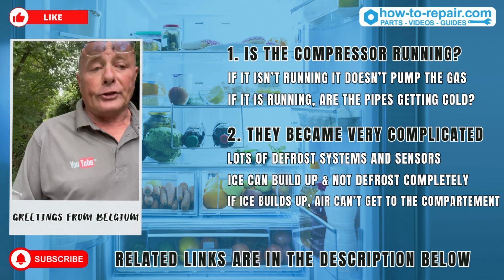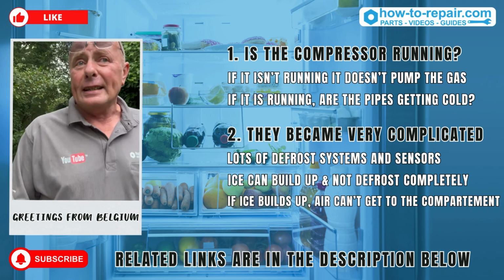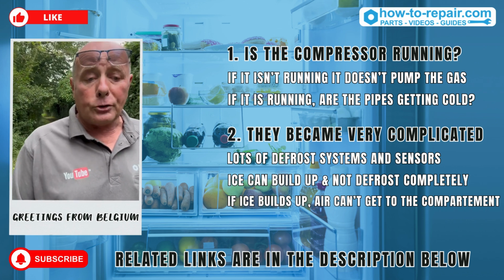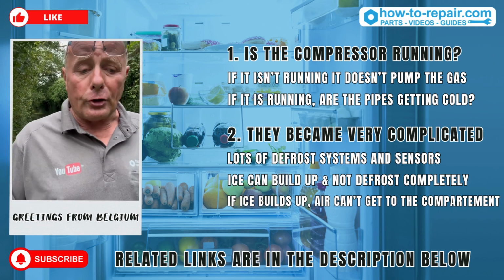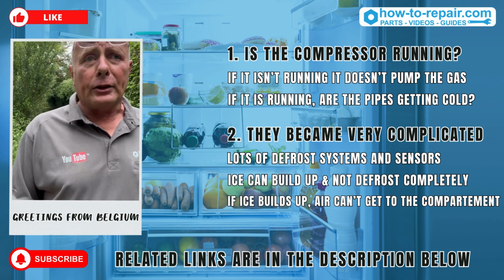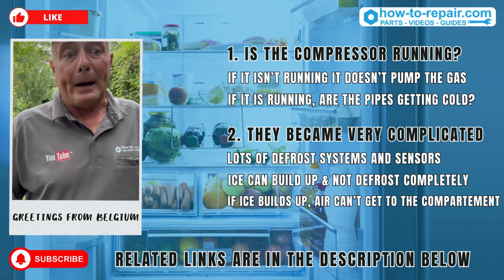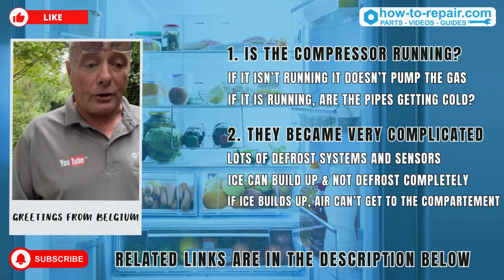You didn't say what temperatures your fridge freezer was running at. All you've said is it's noisy. So please come back to me with much more information. Is the compressor running? What temperatures are being achieved at the pipes? What temperature is being achieved in the freezer compartment? Then I'll be able to help you much better. But I do need detailed information to be able to assist you.